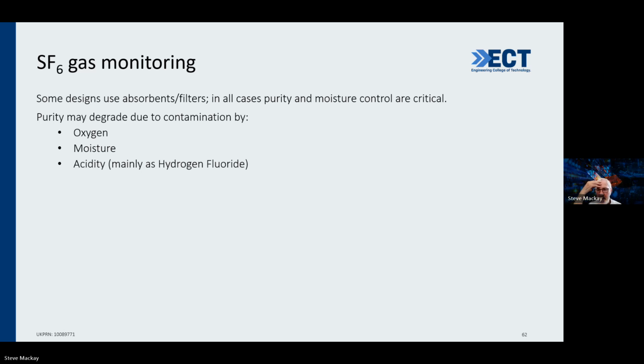Yeah, the hazardous, absolutely right. And what are we replacing them with? Yeah, unfortunately, we still have a lot of installed base of SF6. So even though it's toxic and very damaging for the environment, things don't change overnight. So you've got a huge installed base. As Michael Keenan rightly points out, we're moving towards vacuum or oil and air. I don't know if the performance is as good as SF6, perhaps, although one could obviously debate that, but certainly we don't have a choice. We've got to protect the environment, and obviously it's toxic. So we've gone back to the more traditional items.